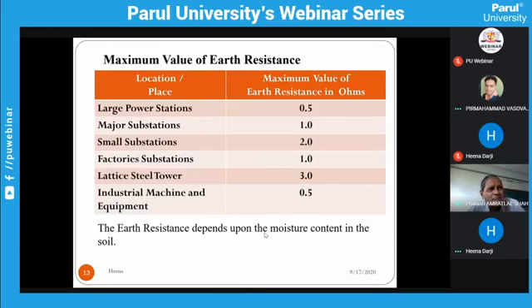Okay, good. Normal earthing, if you see your residence, is pipe type or rod type earthing. But if you visit our 400 kV switchyard, or our 66 kV switchyard, an earthing grid is buried in the substation, while at residential, commercial or industrial sites we are not doing that. If you take the example of the testing bed for the short circuit test, there you have to construct the earthing grid, so that you can have a minimum earth resistance and a very good flow of current, so that the fault current will flow to the relay, and that will give you proper protection.